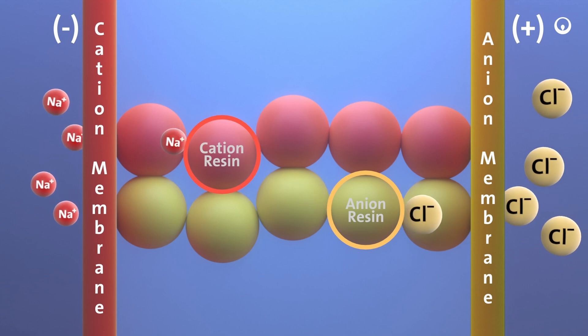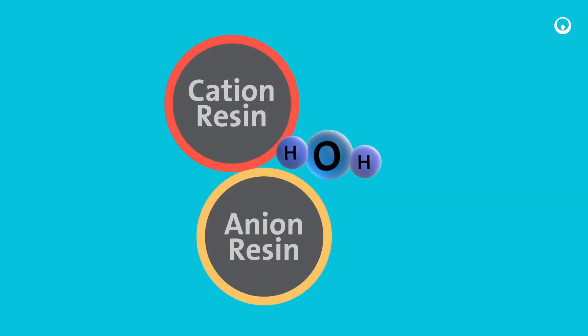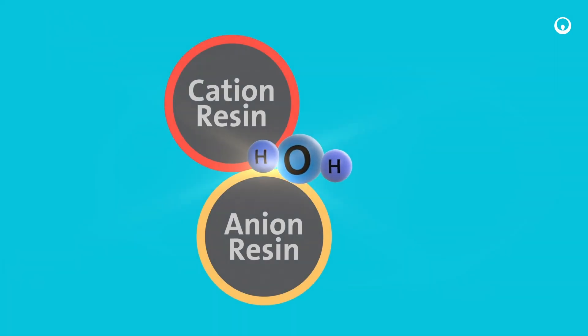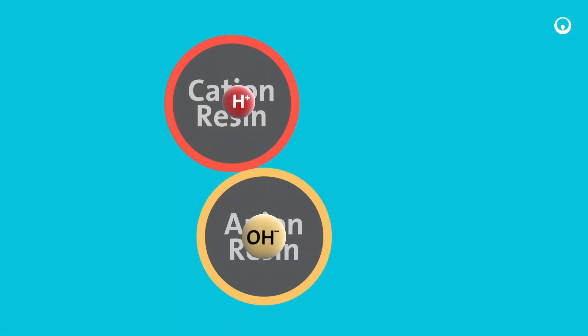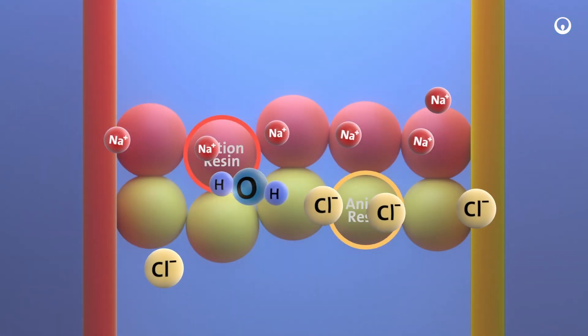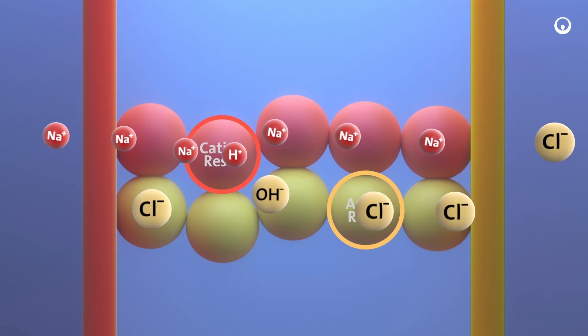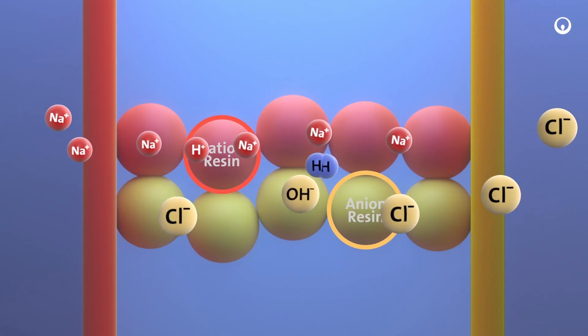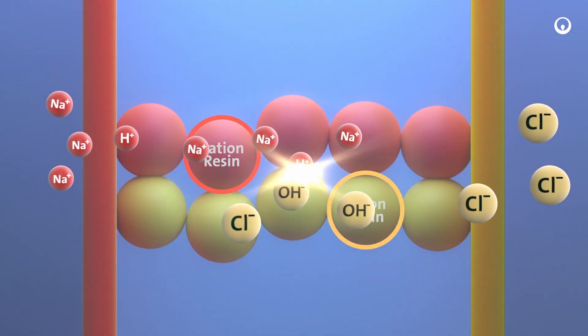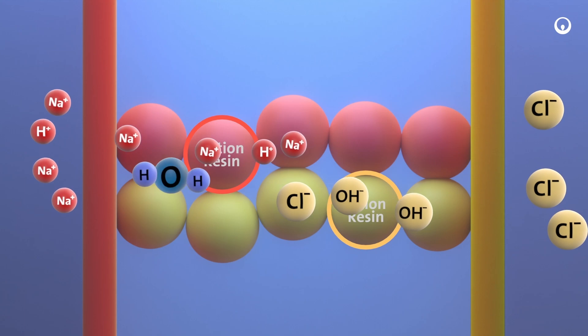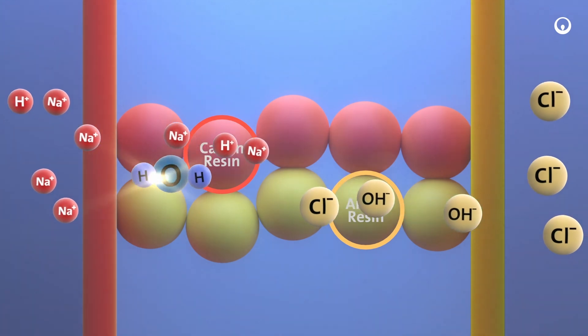The applied voltage drives a water-splitting reaction at the interface between the anion and the cation exchange material, which produces hydrogen ions and hydroxide ions. These ions continuously regenerate the ion exchange resin so that it can continue to remove impurities from the feed water.